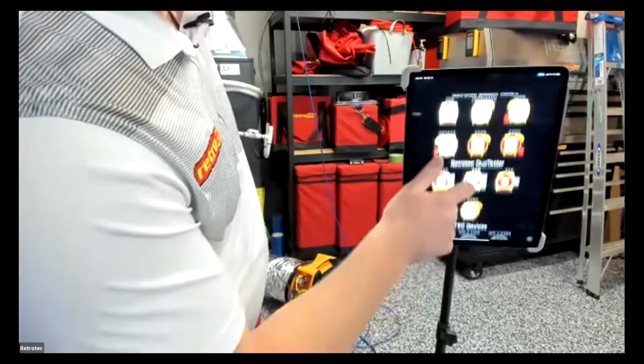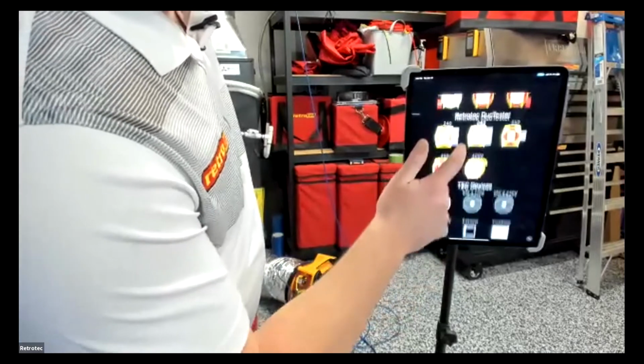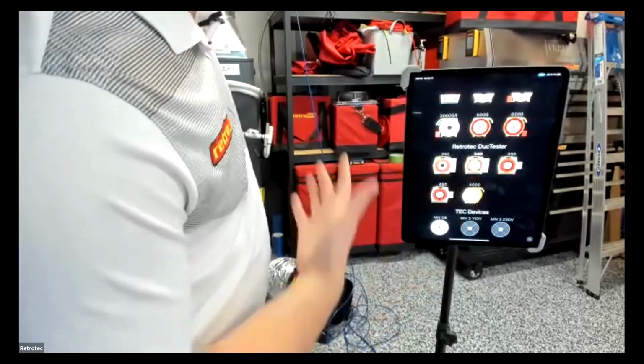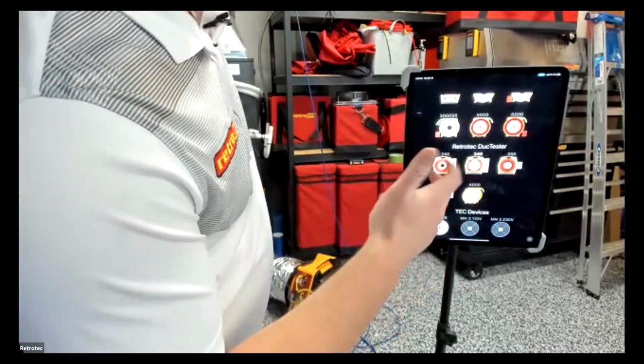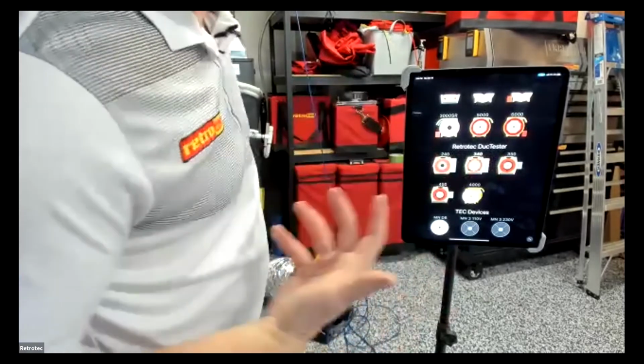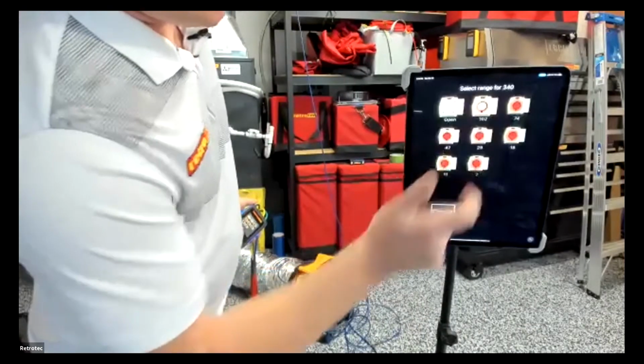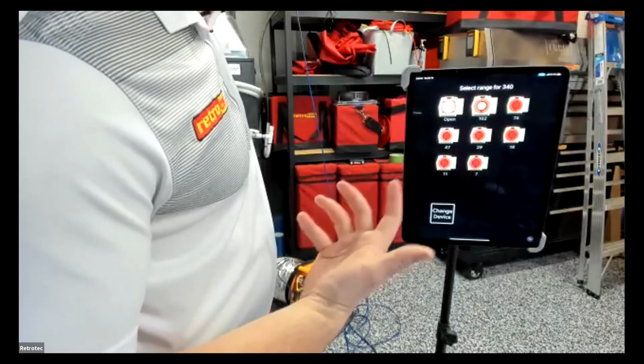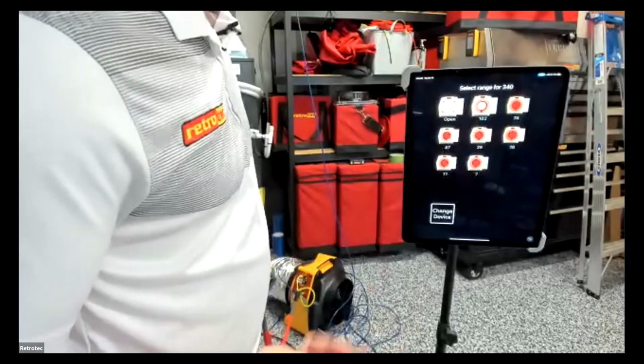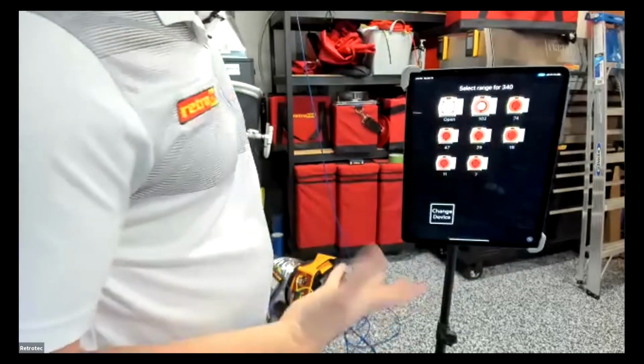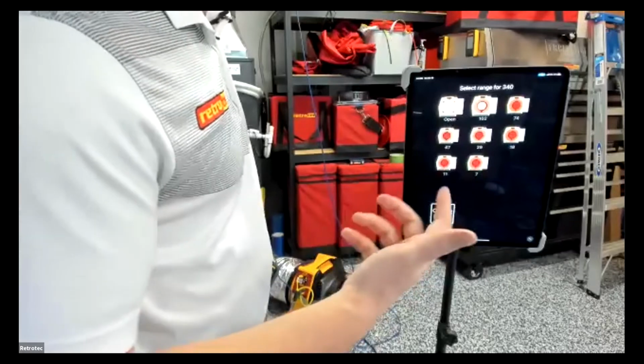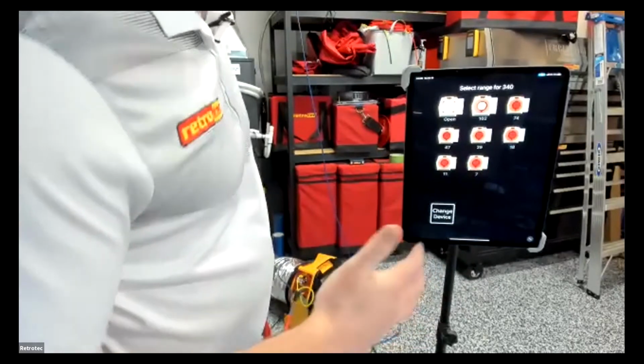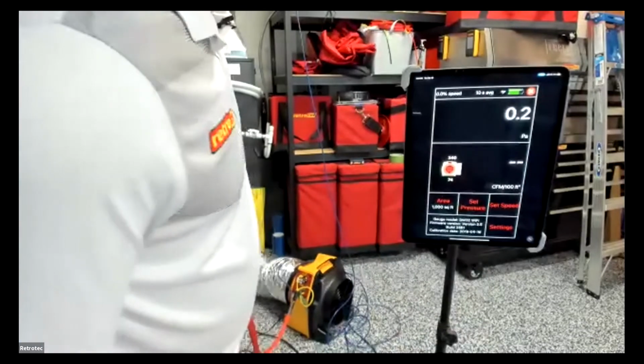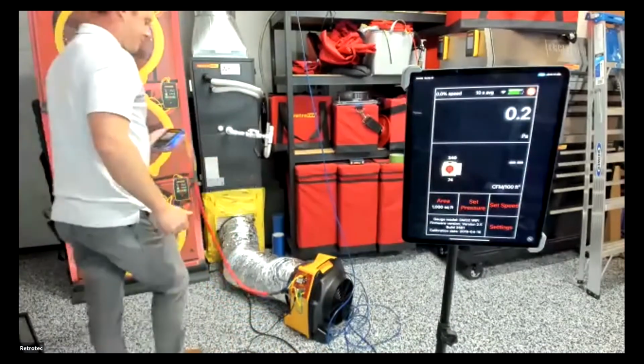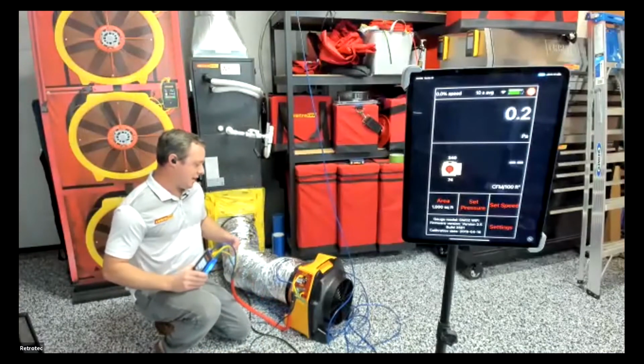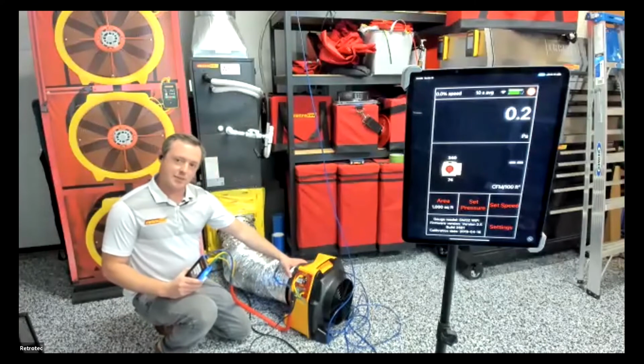So changing the device, there's all the devices you can choose. So you just want to make sure you choose the right one. So this is the 340X. The 340 is what we're going to choose. These other ones are older models or commercial models. So we're doing a residential duct test, so we're going to choose that. And then we have our range that we want to select. So if we're going to run it open at the 102, 74 is usually where I like to start. If it's a reasonably tight system, 74 will do it on a small to medium sized house. And we just want to make sure that that's represented in the fan as well. So if you have 74 selected in the gauge, make sure you have 74 installed on the fan.